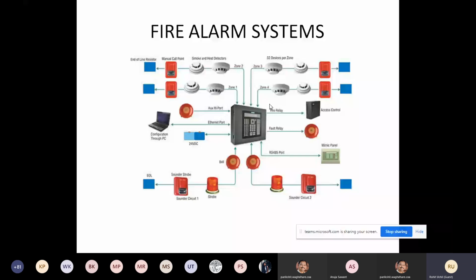There's a fire alarm panel, and that's usually at a place at ground level, which is manned on a 24-hour basis, maybe security cabin, maybe a building manager. And this panel should be visible. You should be able to see the display and the alarms that are coming. Many times, the panel is placed in a closet or in a room which is not occupied, and even though the system works, we don't realize that there is a fire.